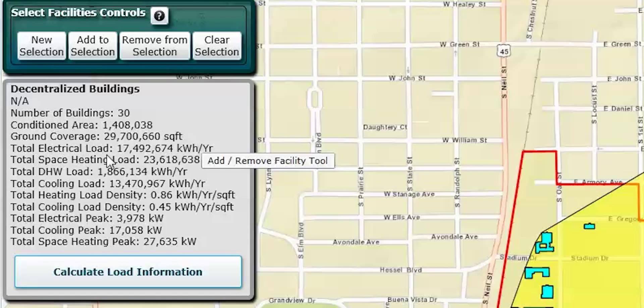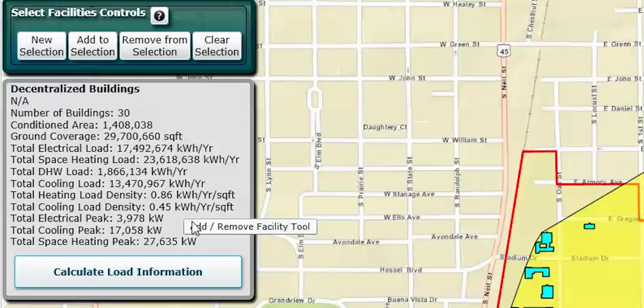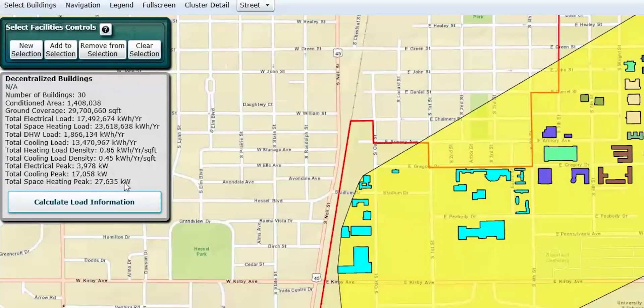You can also see the total electric load over the course of a year, the space heating load, domestic hot water, cooling load, and some density information. These are the heating load density and cooling load density over this larger area, which is more important when looking at centralizing systems. We can also see the total electric peak — that's the high point for the year — as well as cooling peak and space heating peak.